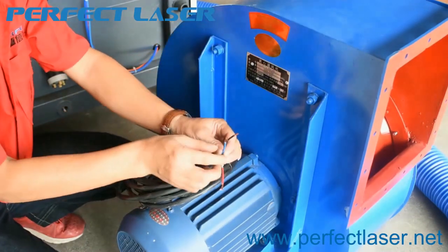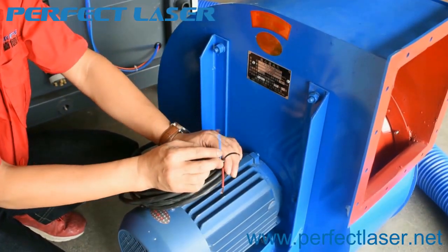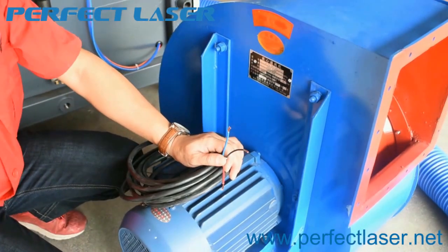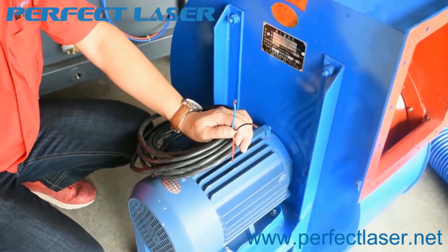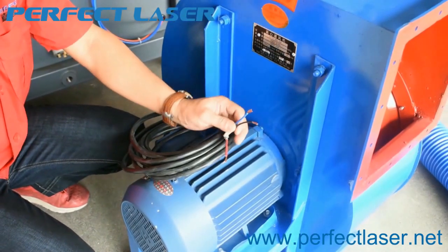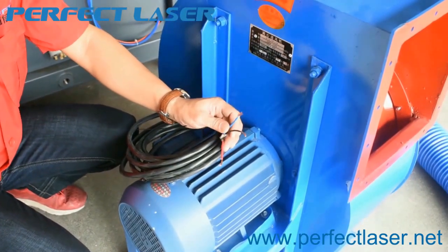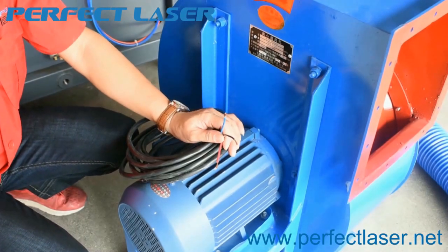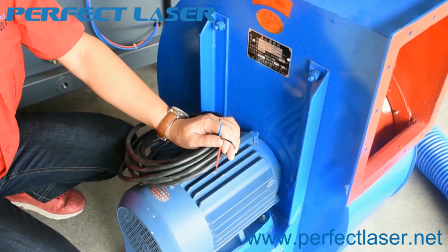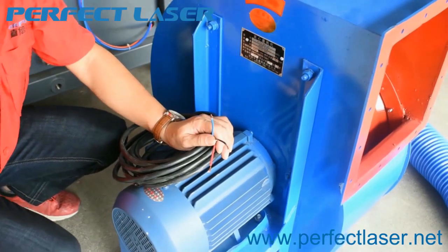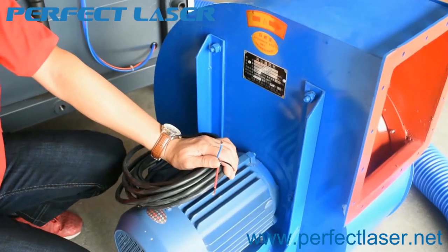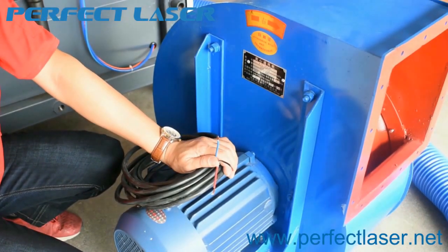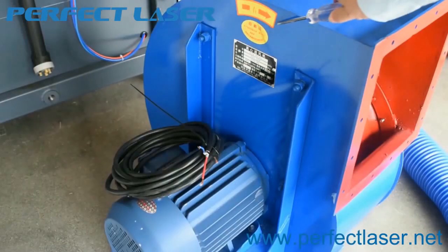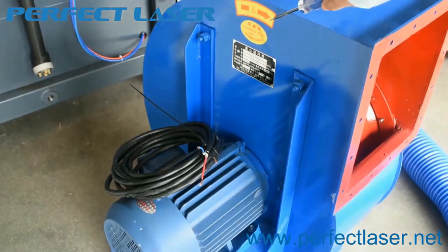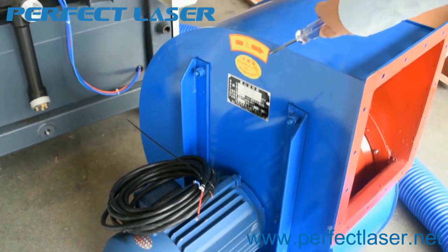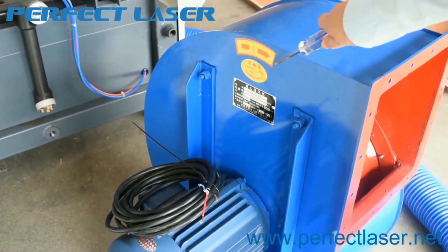If the fan turns left, that means it's not okay. You can change the cable sequence. Swap any 2 cables, and that will make the fan turn right. Please make sure the fan turns in the right direction. Here is the arrow. Please make sure the fan runs according to the arrow.